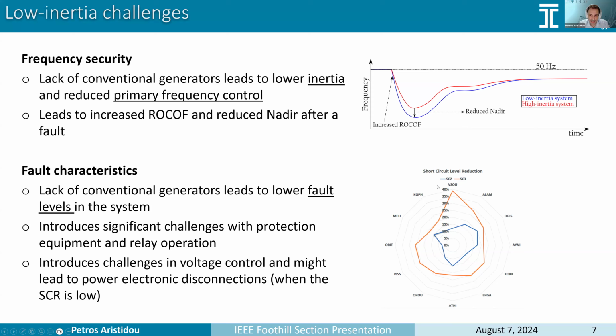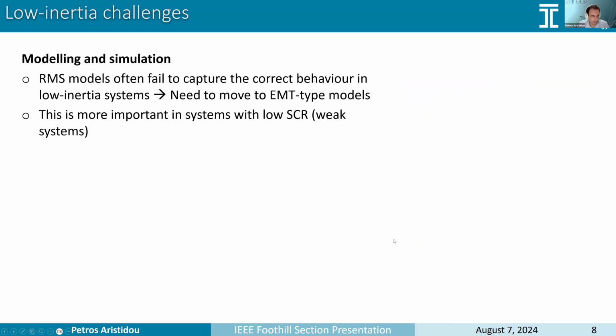For example, this is again from the Cyprus system. This is the short circuit level reduction at different substations in Cyprus compared to 2020. We see that currently there is a maximum fault level reduction of 20% in some substations. And in orange are the forecasted values for 2028, so in 4 years. We see that it's expected that some substations will have a 40% reduction in their fault levels. So we need to be careful, and we need to make sure that the protections can still operate, and we need to introduce changes into the system.